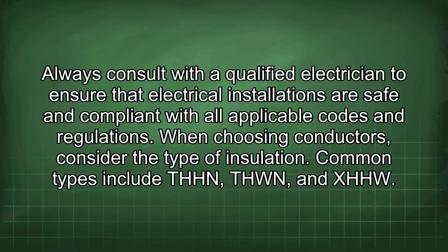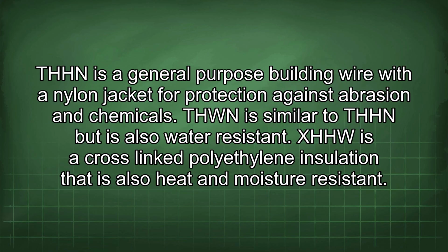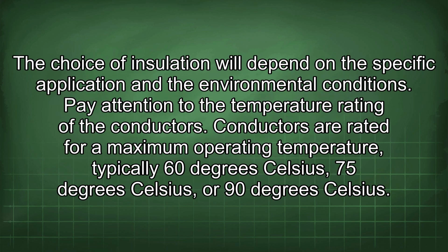When choosing conductors, consider the type of insulation. Common types include THHN, THWN, and XHHW. THHN is a general-purpose building wire with a nylon jacket for protection against abrasion and chemicals. THWN is similar to THHN but is also water-resistant. XHHW is a cross-linked polyethylene insulation that is also heat and moisture-resistant. The choice of insulation will depend on the specific application and the environmental conditions.